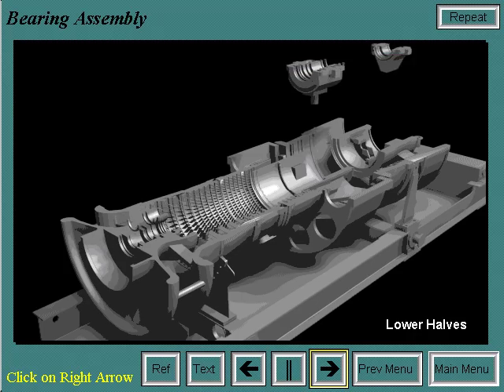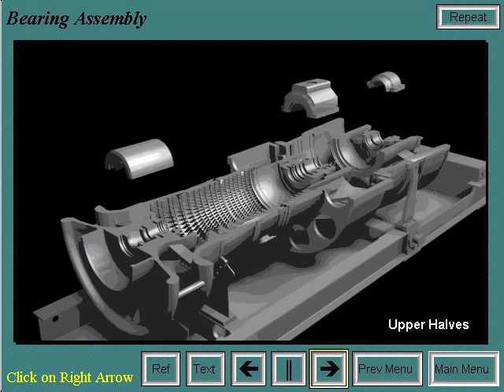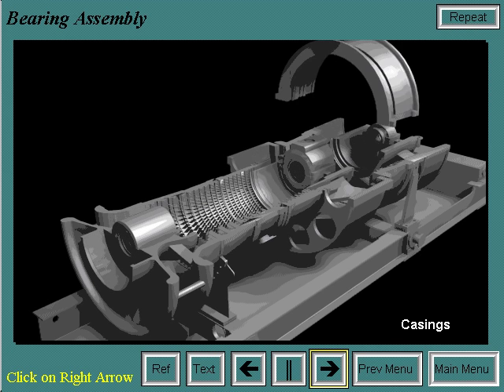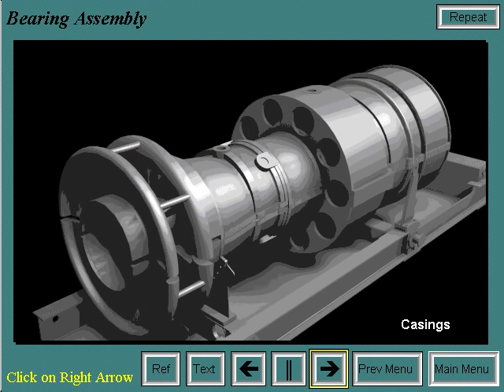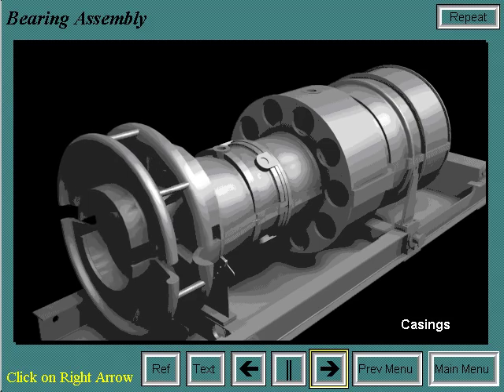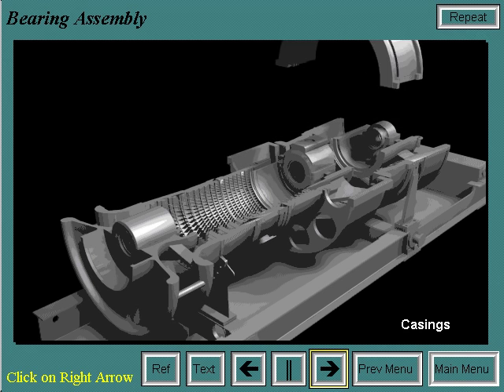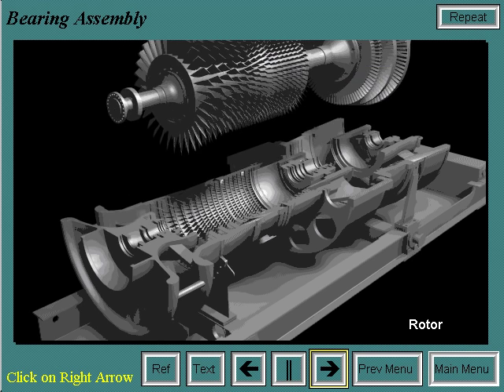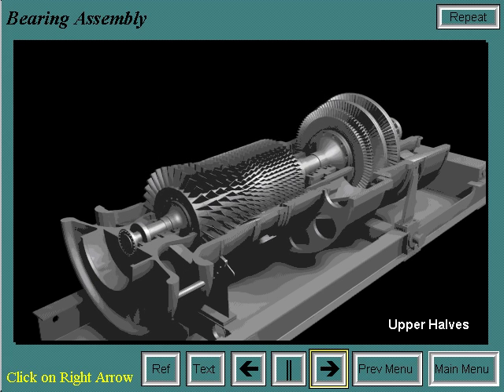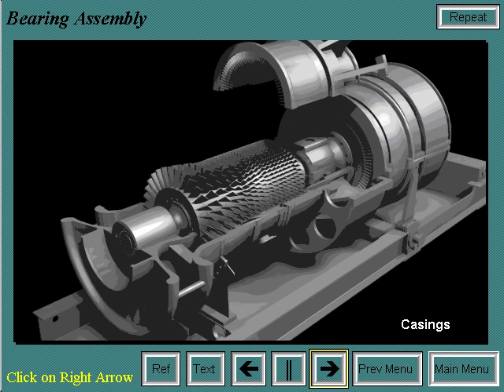The number one bearing is installed in the inlet casing, and the number two and number three bearings and housings are placed into their respective casings. The lower half is put in first, then the upper half of the bearings and housings are installed. The bearings are aligned with the casings installed. The upper halves of the bearing housings and casings are then removed and the air seals and oil deflectors are installed. The final step is the installation of the rotor and the upper halves of the bearing housings and casings.